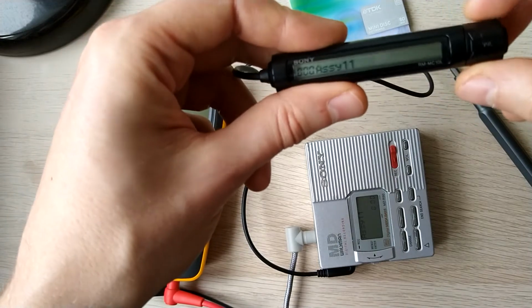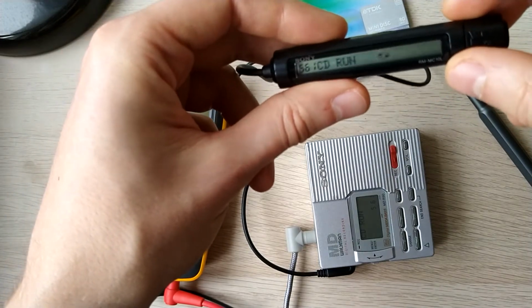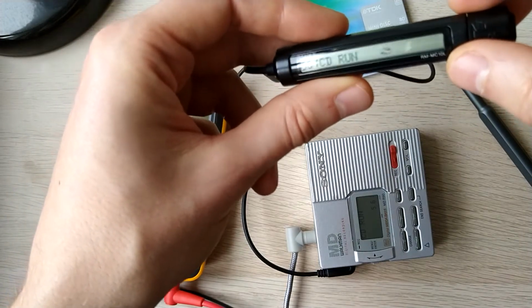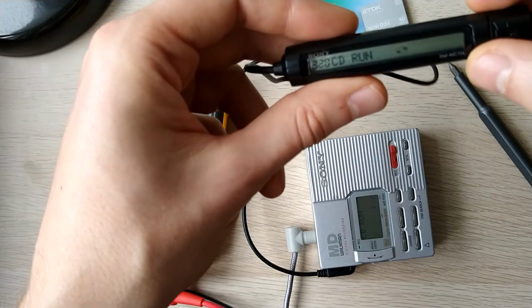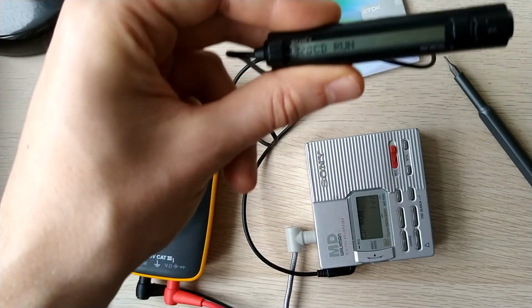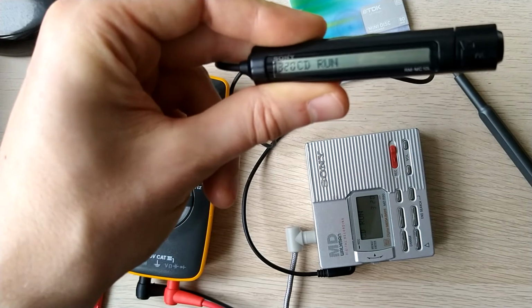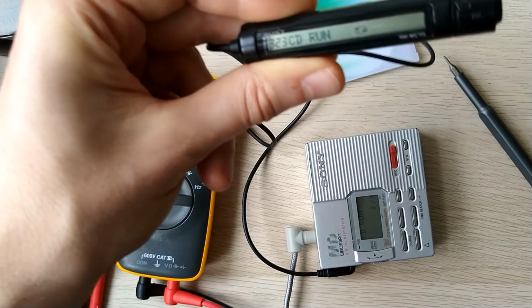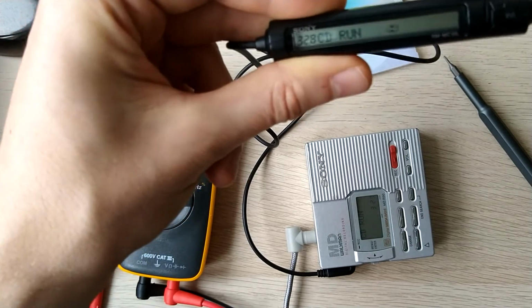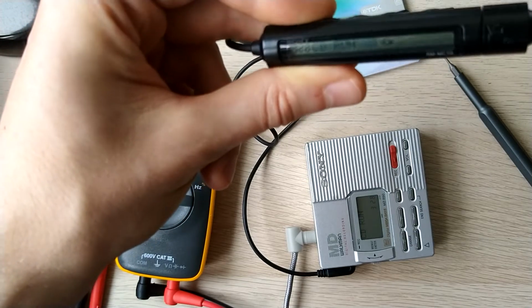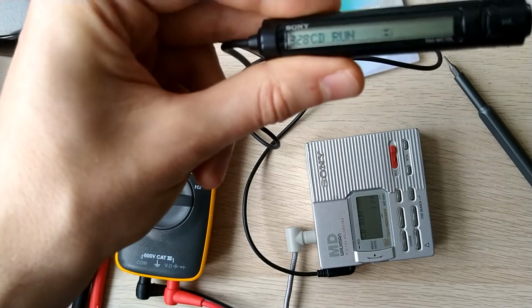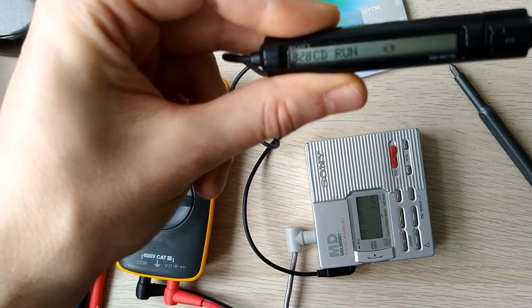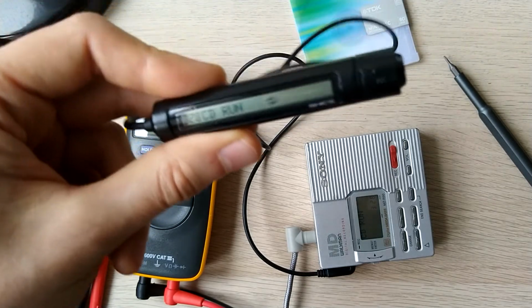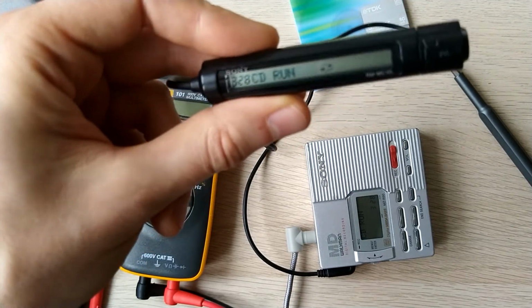So once we press play, it will begin the first half of the adjustment process, which is adjusting for pre-recorded MDs. This process is fully automated. You can see that the numbers on the left-hand side are changing, so the device goes through different settings and attempts to auto-calibrate them.